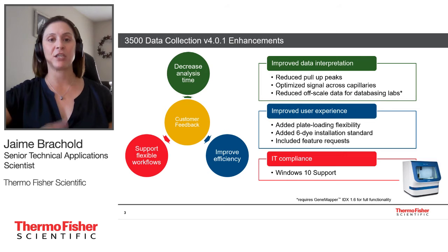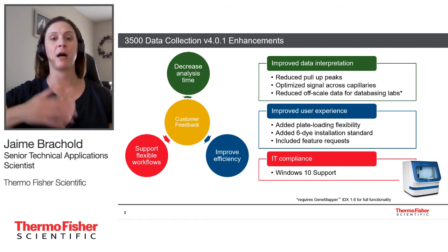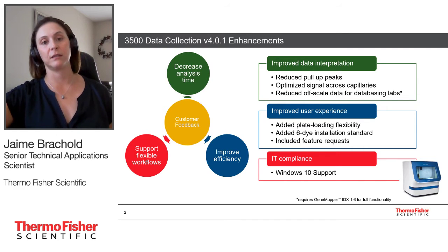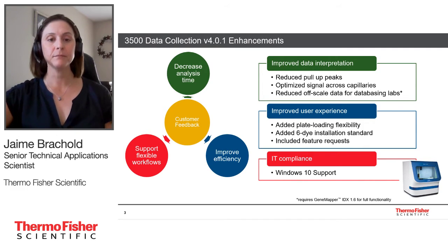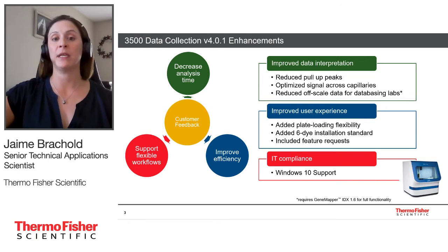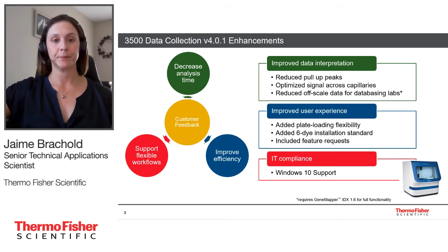We included, like I mentioned, other feature requests, things like being able to export the injection list, have a consumable log that is very easy to read to see when consumables were taken off or put on the instrument and by whom. So those are a couple other ones, but there is a full list of all the new features in the data collection user bulletin. This data collection version 4.0.1 is Win 10 supported.